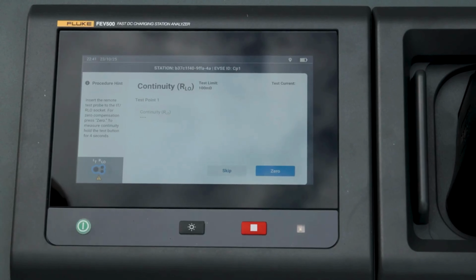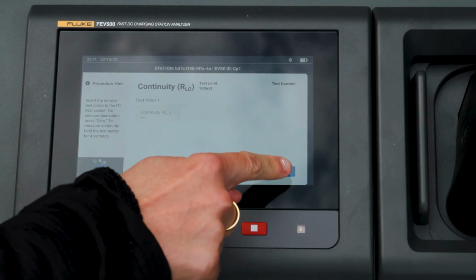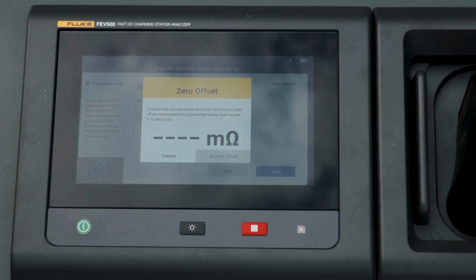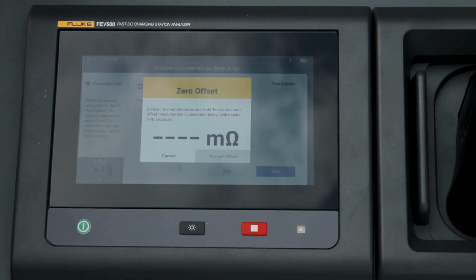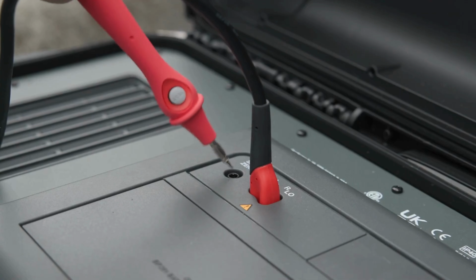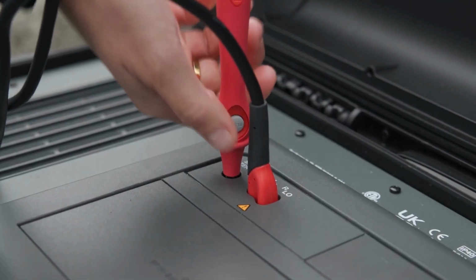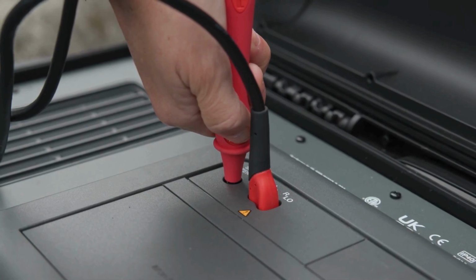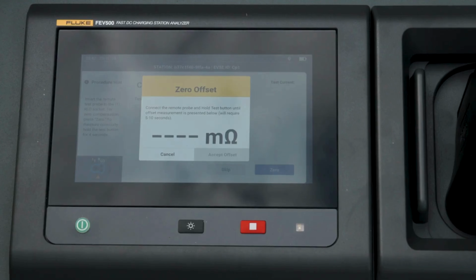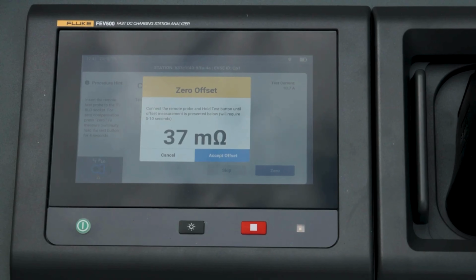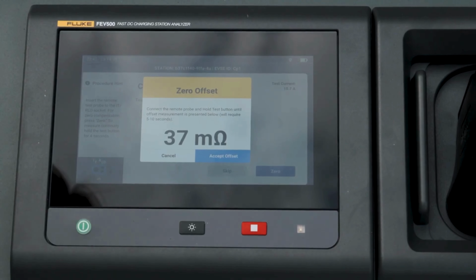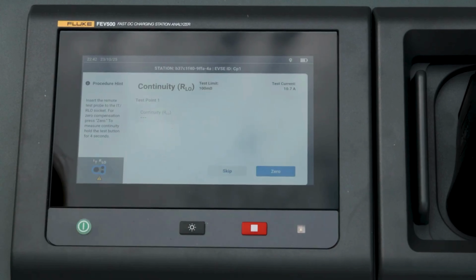The first thing I'm going to do is zero out or null the test probe to make sure our measurement is accurate. I'll select 0, and it's asking me to connect the test probe to the R-low input jack, with the tip going into the sense 0 input, so I can null or zero out my test probe. Once inserted, I press the test button and hold it for a little over 5 seconds on the remote test probe until the measurement pops up. You can see we see 37 milliohms, so I'm going to accept that offset.